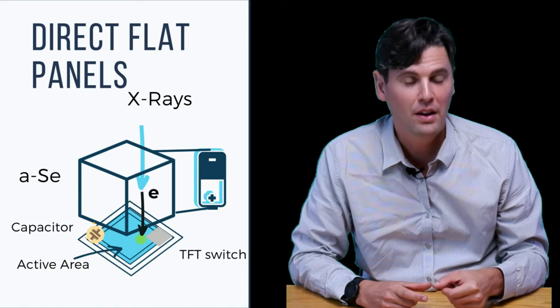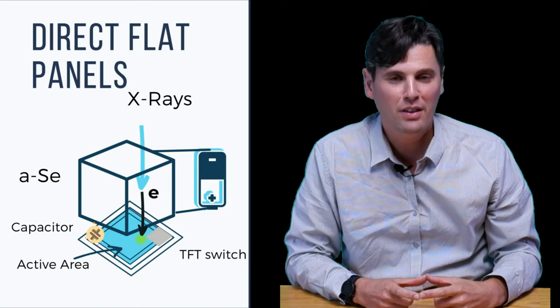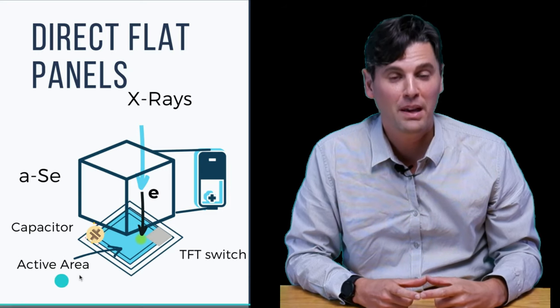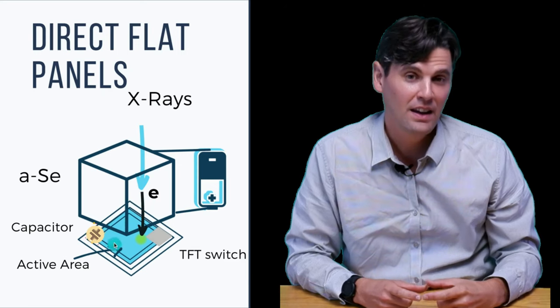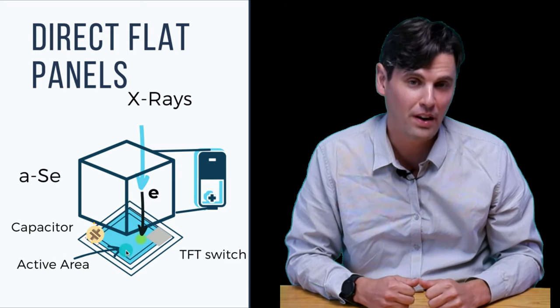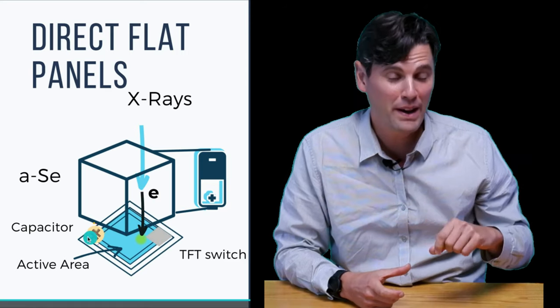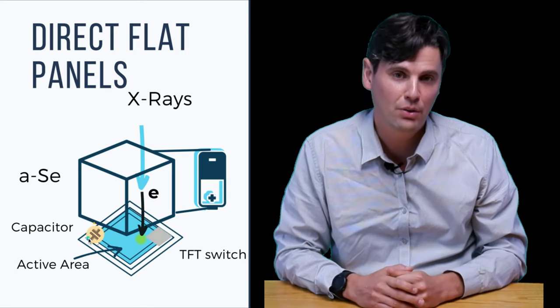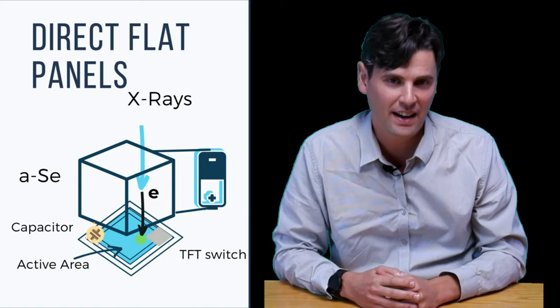In direct flat panels, compared with indirect panels, we skip the step of having a silicon photodiode because the electrons are measured directly. Those electrons are measured within the active area of the TFT array, charge is stored in a capacitor for each detector element, and the gate or switch is used to address and read out each detector element.